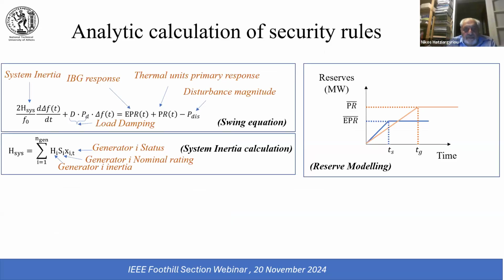A few words about the analytical calculation. The classical swing equation includes system inertia, change of frequency, the load damping, and then you have the response of the thermal units and the inverter-based units. And this is the disturbance magnitude. What is important to observe on the right-hand side is that these two types of reserves, thermal units and electronic-based units, have different response times and different speed of response. So T_S and T_G are the times when they reach their available reserve, okay, the reserve modeling.